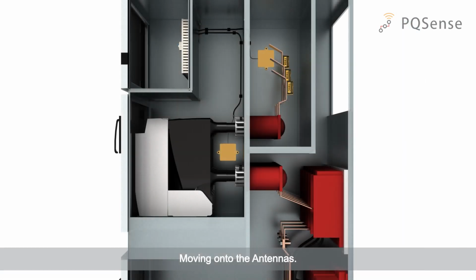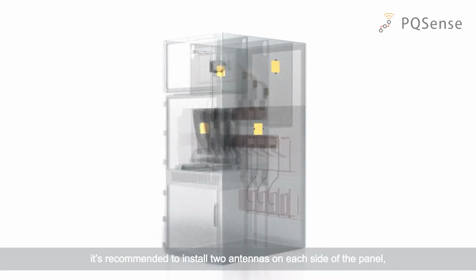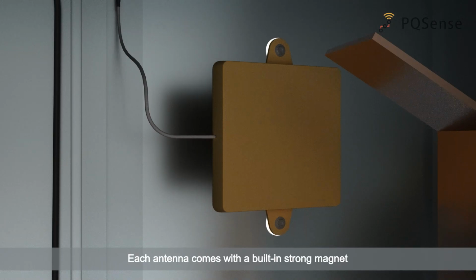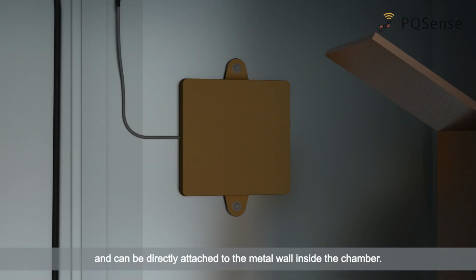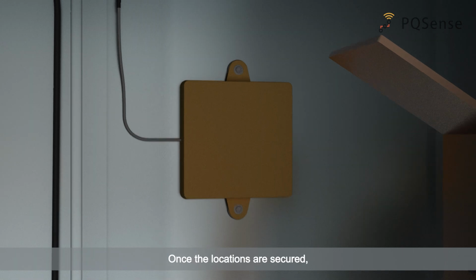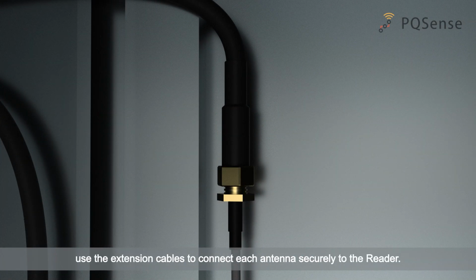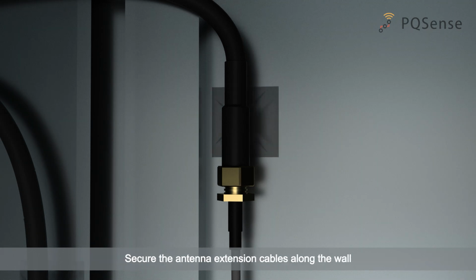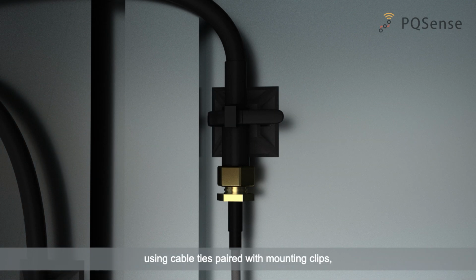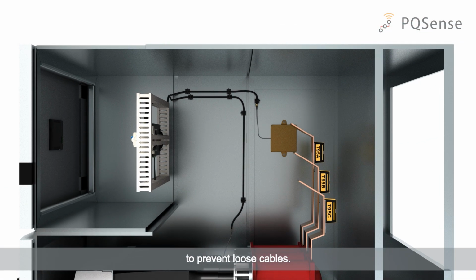Moving on to the antennas. Antennas should be positioned based on the actual location of the sensors. To ensure stable signal transmission, place each antenna facing the sensors within the same compartment. In most setups, it's recommended to install 2 antennas on each side of the panel per compartment to ensure maximum stability and redundancy. Each antenna comes with a built-in strong magnet and can be directly attached to the metal wall inside the chamber. Once the locations are secured, use the extension cables to connect each antenna securely to the reader. Secure the antenna extension cables along the wall using cable ties paired with mounting clips to prevent loose cables.